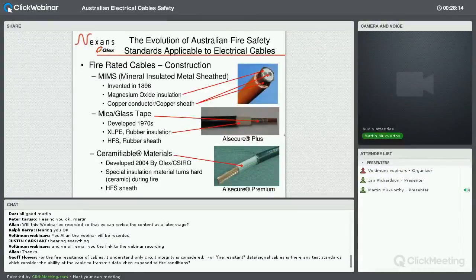I've got one slide here that talks about how fire-rated cables are constructed, and I summarise this into a fairly concise single slide, because when you look at it, there's literally only three types of ways in which fire-rated cables or cables with circuit integrity have been developed over the past 100 years. And some people might be surprised to learn that MIMS cable, which is a mineral insulated and metal sheath cable, was actually invented prior to the 1900s. And I think maybe the inventors didn't quite realise what they invented at the time.